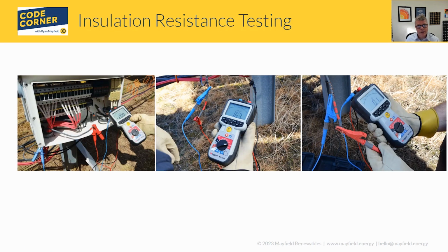So real quick, this is meant to be a high-level overview for insulation resistance testing. This is not meant to be the only training that you get by any means. But in this slide, we have a few images of tests at PV sites. Hopefully you can see it there on the screen if your screen's not too small. We're doing 3 different tests and getting 3 different readings. On the far left test, we're getting over 200 gigaohms. You can see it just says greater than 200 gigaohms. That specific meter, that's the highest it can read, so we've pegged that meter out. We don't even know what the actual resistance is. It's a very, very large value.